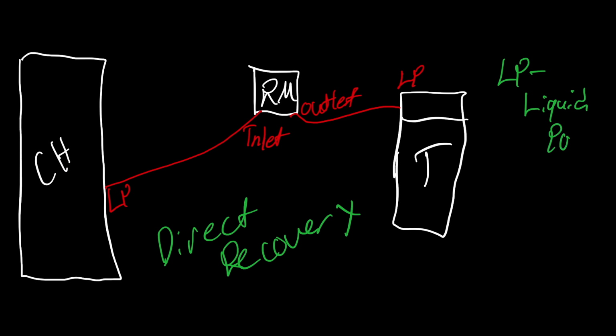With air-cooled chillers, because they only get so big, they top out around 550 in terms of total tonnage. The biggest refrigerant charges I've seen for air cooled are around 400 or 500 pounds at the top end. With a lot of newer designs, they're finding ways to cut back on that charge even further while still maintaining capacity. Regardless, I don't think you need to invest in an industrial recovery system just to do air cooled service. If you're doing water cooled and getting into really big centrifugals, absolutely, but not for air cooled. A lot of times where they're located, it's just impractical to get those big systems up there.